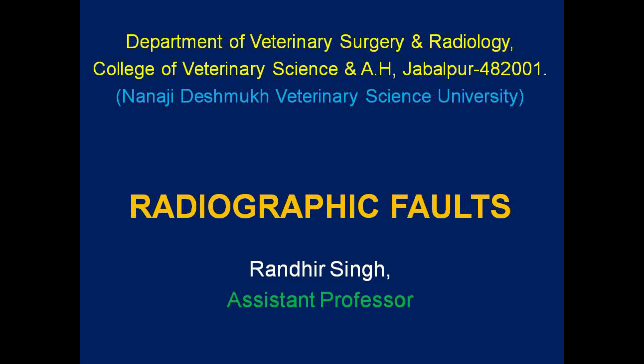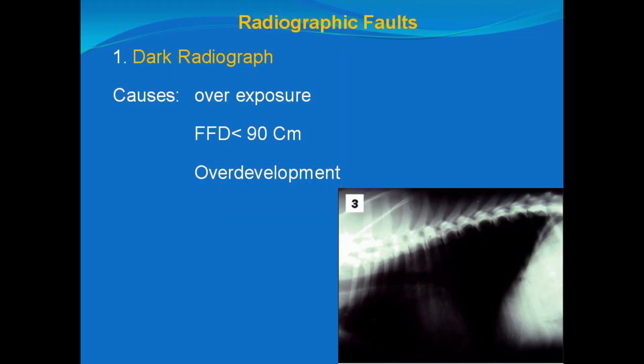Good morning friends. I will discuss the problem of dark radiograph. We get a dark radiograph due to three or four common reasons. Sometimes our exposure factors are quite high — we may be using high kVp, higher mA, or simply more exposure time. The second reason is our FFD may be less than 90 centimeters. The third reason is we may be over-developing the film, meaning we are keeping the film in developer for a long time, or our solutions may be at a higher temperature than normal.